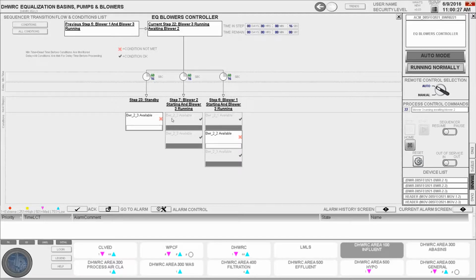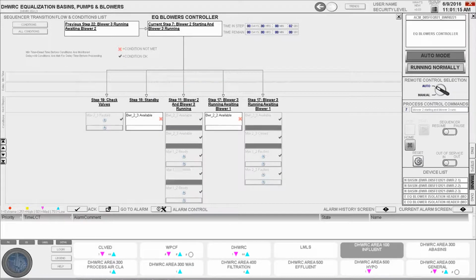And here we can see both conditions are met to go to step 7. All we're waiting on is the minimum step time to pass, which we'll fast forward through for this demo. Once the time has elapsed, you see we go to step 7. And after only a couple seconds we head to step 11, where the system is running normal again.